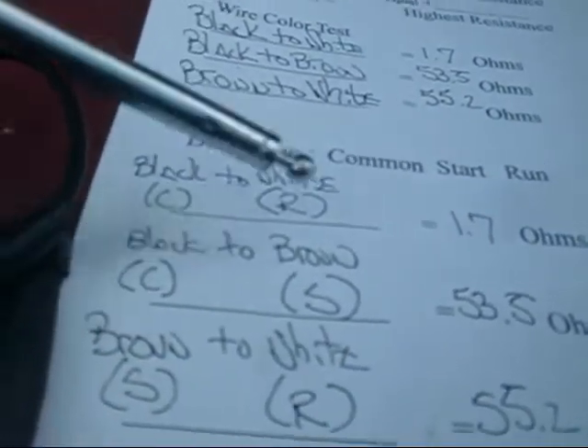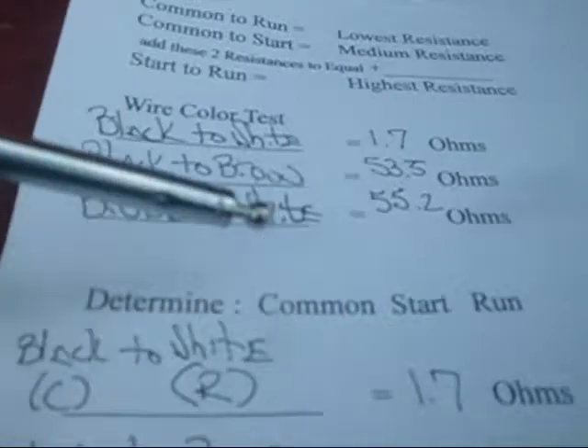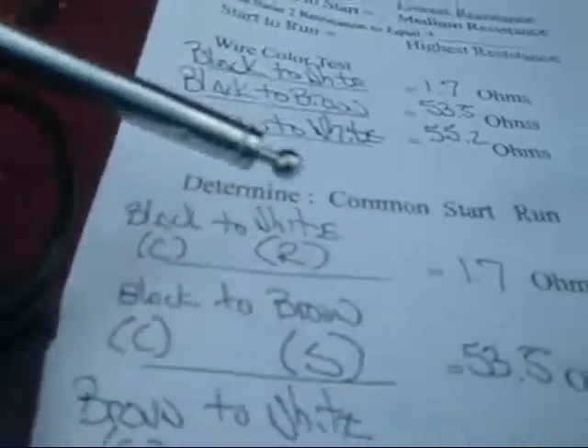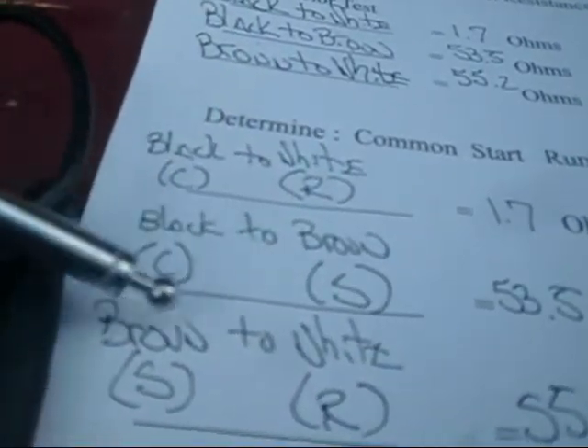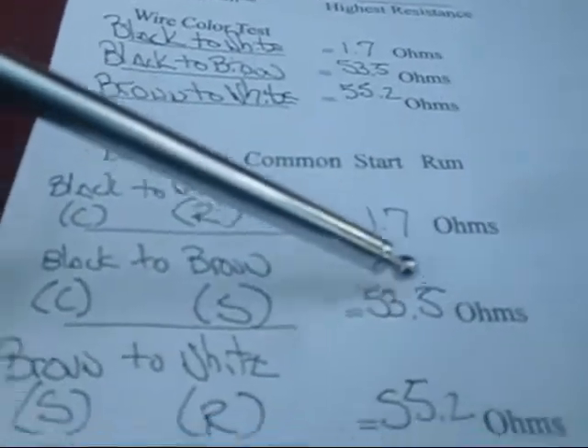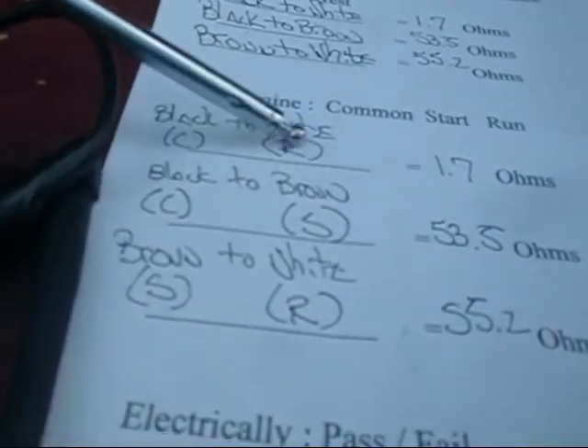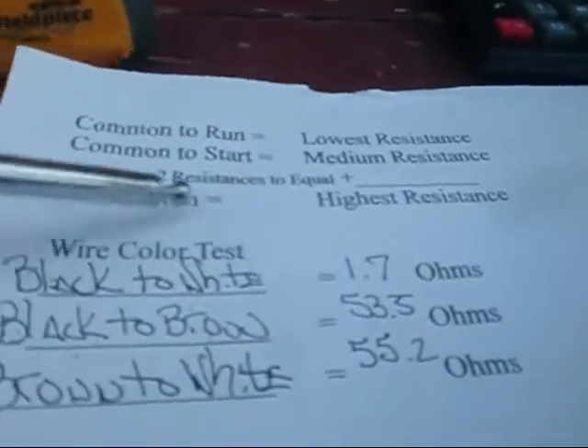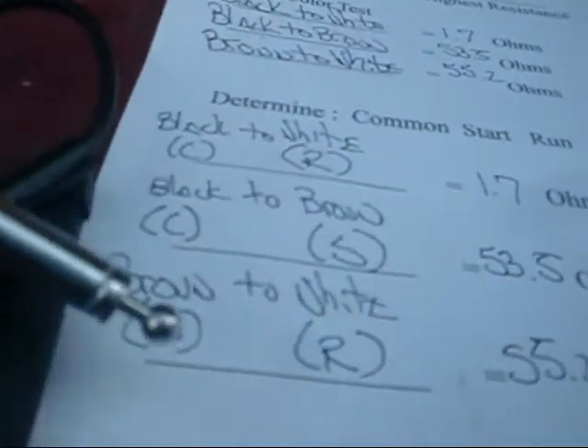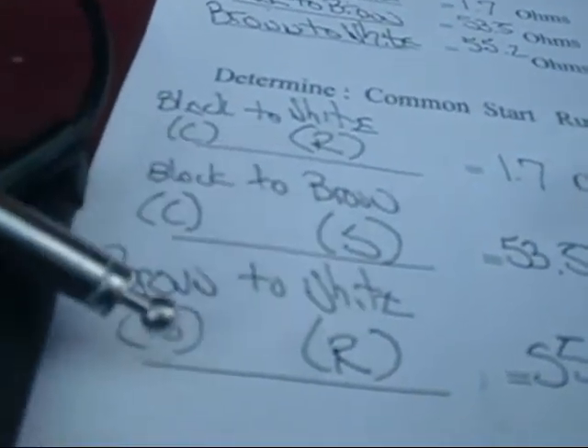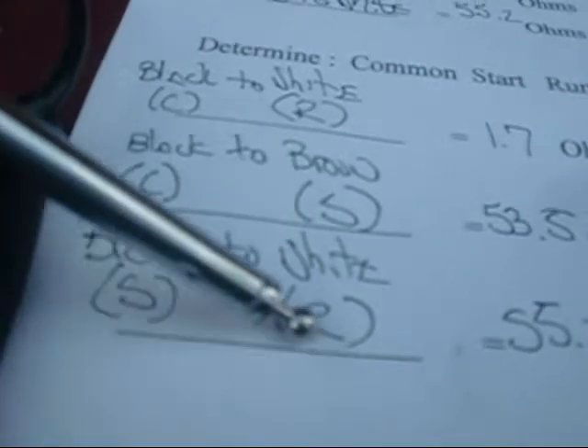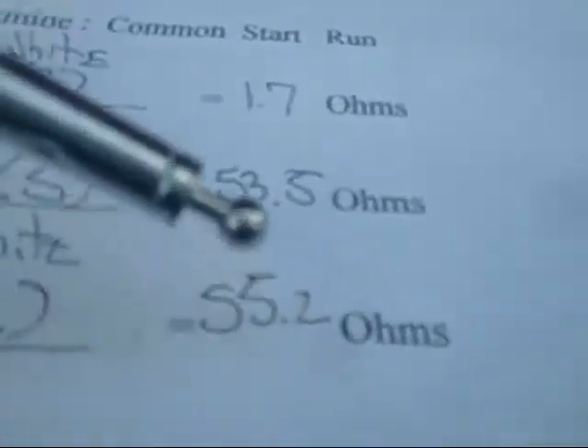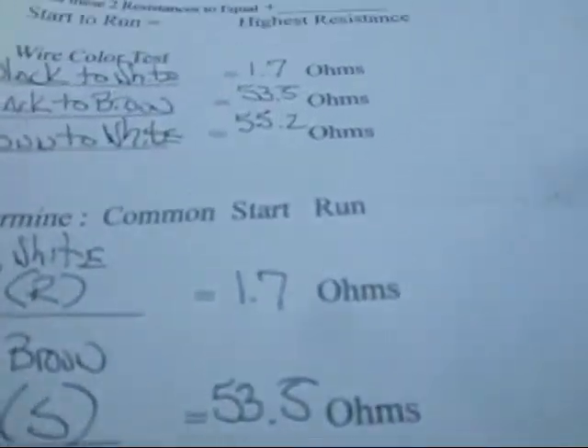Black to brown, common to start, medium resistance. So we said black is common, brown is start, 53.5. We have the two left over which is our start to run, highest resistance. So we determined brown to white. Brown was start, white was run, and we came up with 55.2 so we know this motor's sound.